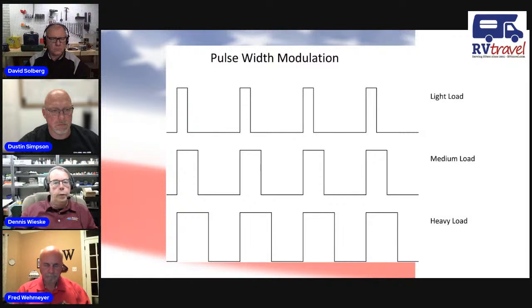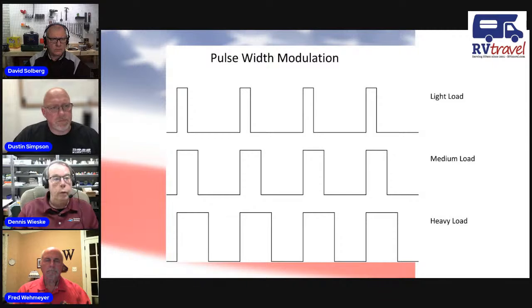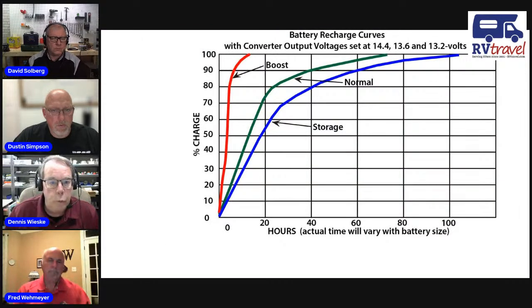So just to note, anytime you see a correct voltage on the output of the converter and your battery's not charging, there is a problem between the converter and the battery, not the converter. That converter is putting out the correct voltage, and that current is available, because anytime you put a load on it, we put out more power up to the maximum rating of the charger. That's basically how the charger works.